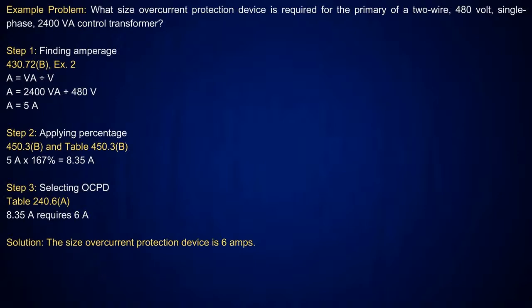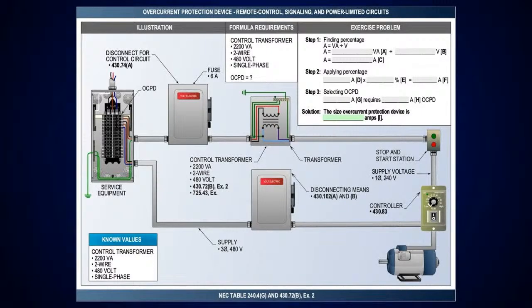But when you look at that table, you're going to notice there's no superscript 1 there like we talked about the other day. So if there's no superscript, what do I do? I drop down again. Yep. Okay. So you take the 5 amps at 167%, that's going to give me 8.35 amps. So the next size below that, standard size per table 240.6A, is a 6 amp overcurrent protection device. Okay. Right.